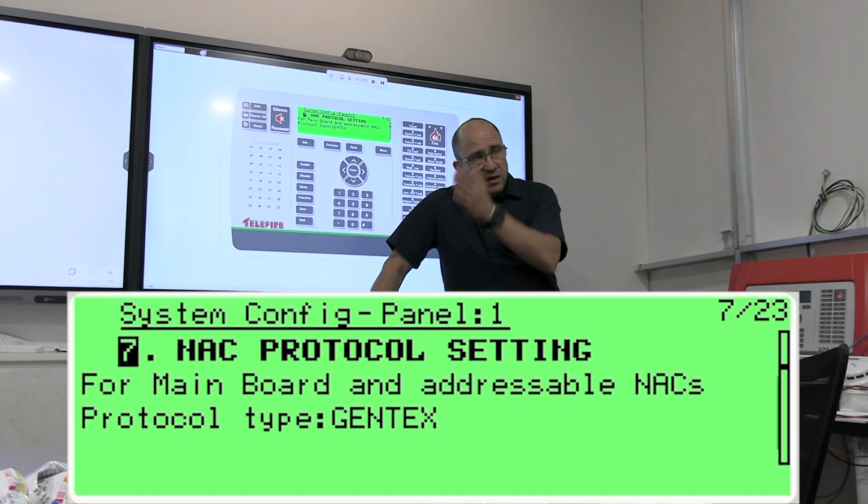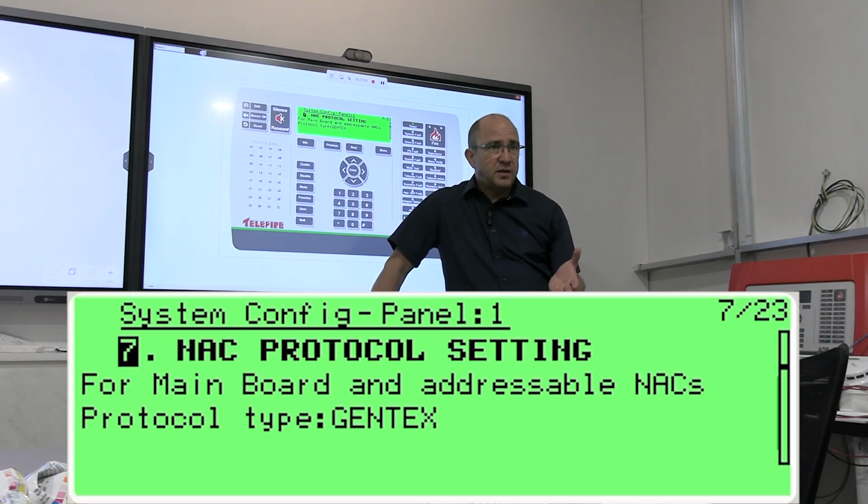It's a fact. We programmed it to work with this brand and this brand because it's a language. We taught the control panel 2 languages. One language that speaks with the Gentex siren, and one language that speaks with the Wheelock siren.